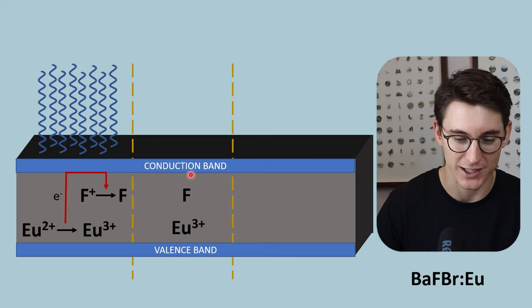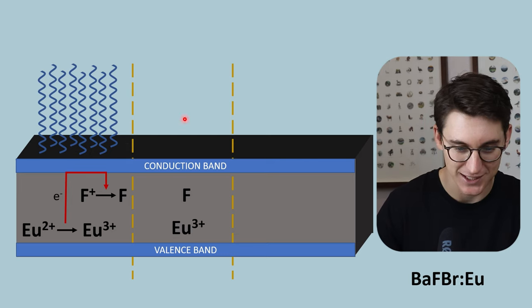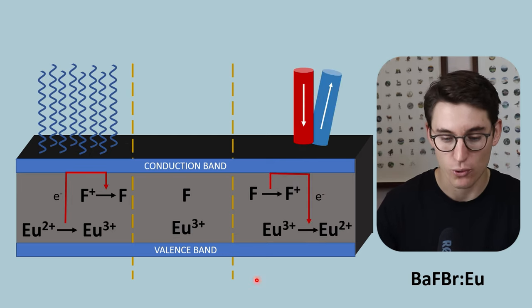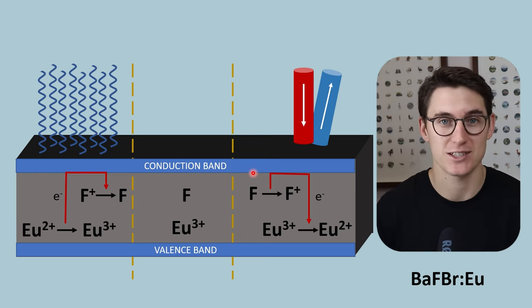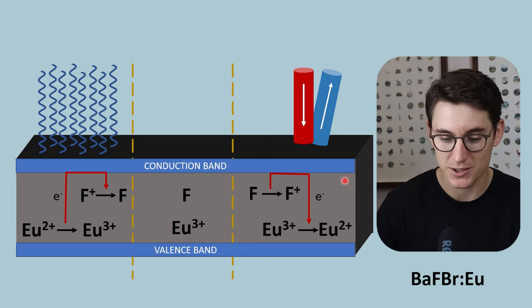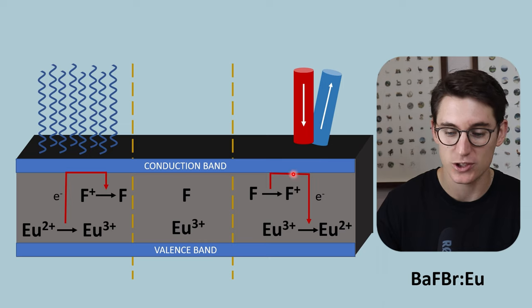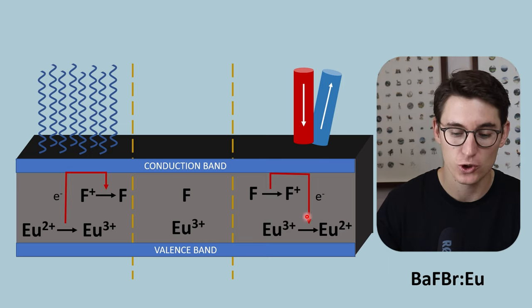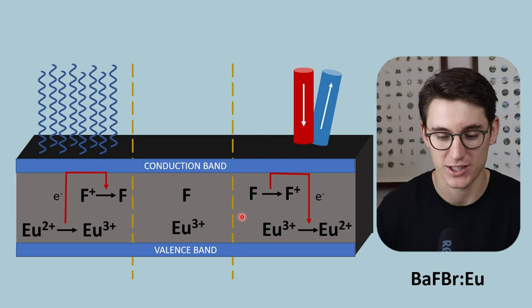Now we've created our latent image. The dotted lines represent three different periods in time: acquiring the x-ray, latent image formation, and then processing that x-ray. This can happen at any stage once we bring the cassette to our CR reader. This process can also be reversed — we can release an electron from our F-centers by giving energy into the system, and those electrons can drop down to a lower energy state and release energy.